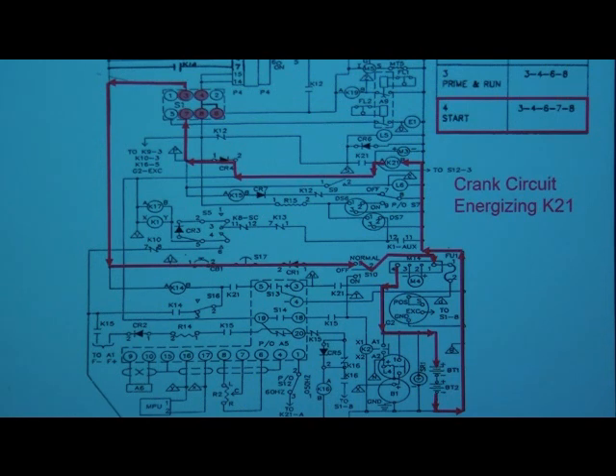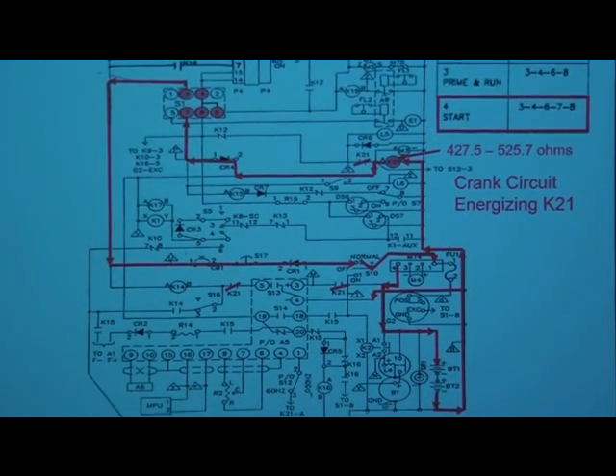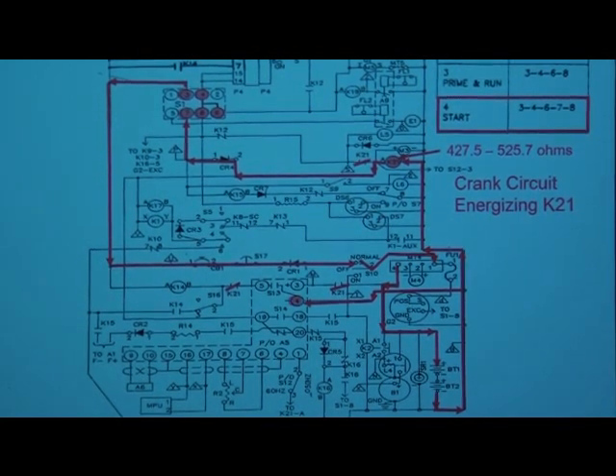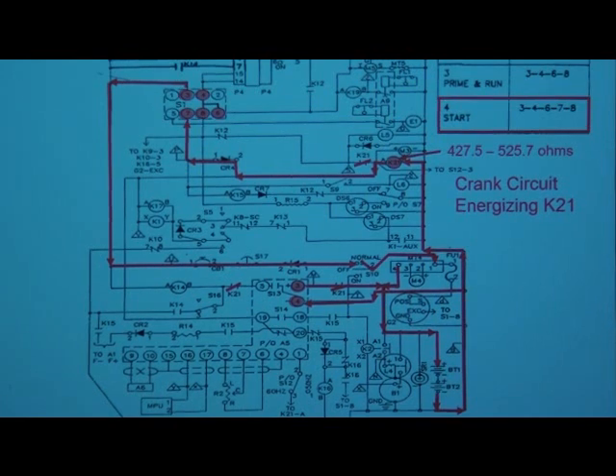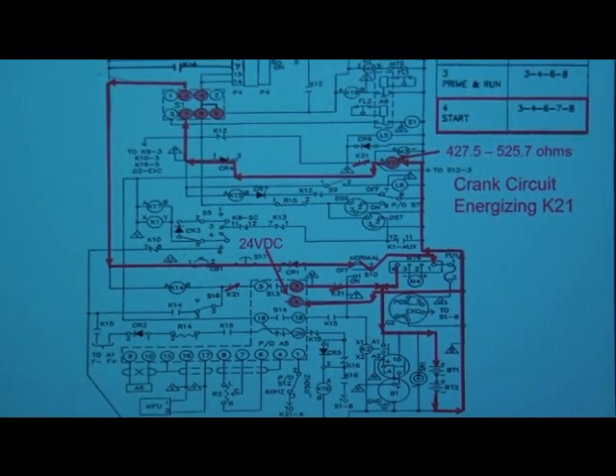Our K21 is now energized. Now that our K21 electronic governor control relay is energized, our contacts will now reverse, opening normally closed contacts and closing normally open contacts. This allows input power to our Alpha5 electronic governor. We will pick up potential from the CB ground going towards our Alpha5 electronic governor pin 4 and leaving out of pin 3 towards the positive side of the battery. With the Alpha5 electronic governor control having 24 volts DC, the S14 crank disconnect switch contacts now reverse.